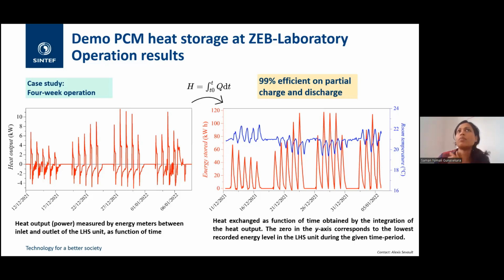We can secure 5 to 10 kilowatts for quite long if we need to. And then, I remember you mentioning 15 to 20 hours of charge or discharge, so that's with playing around with this temperature on the water, just 2 to 3 Kelvin then.